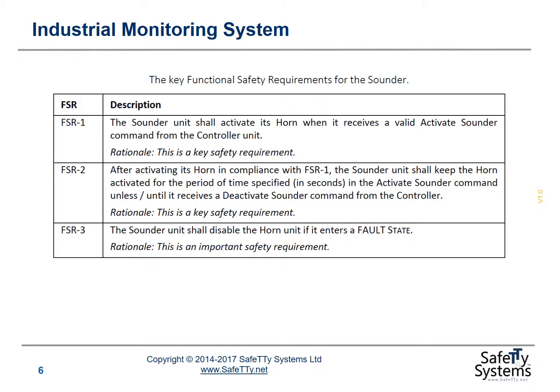We've identified the following functional safety requirements for the sounder. Functional safety requirement one: the sounder shall activate its horn when it receives a valid activate sounder command from the controller unit — this is clearly a key safety requirement. Functional safety requirement two: after activating its horn in compliance with FSR 1, the sounder unit shall keep the horn activated for the period of time specified in seconds in the activate sounder command, unless it receives a deactivate sounder command from the controller. Again, this is a key safety requirement.